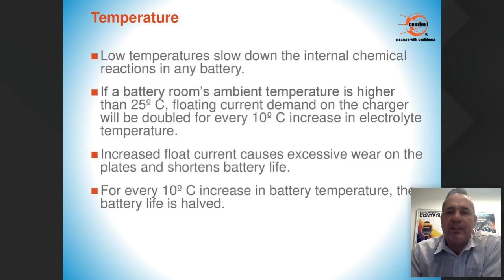Battery degradation. The main cause of battery failure is heat. For every 10 degrees Celsius average temperature increase, battery life is halved. It causes the electrolyte to be expelled from the battery. It degrades the plates, the anode and cathode in your battery. Overcharging, sulfation. It turns lead oxide into crystal form, and these attach to the plates, effectively lessening the capacity they are capable of delivering.